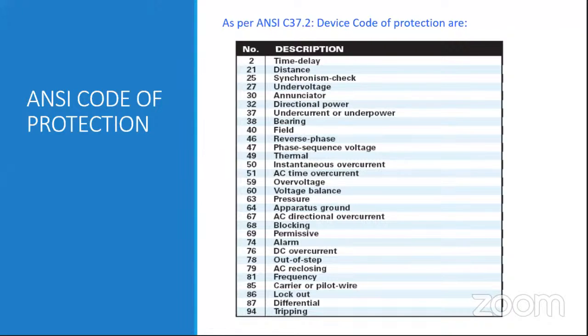Or we can say apparatus ground, in this it means the equipment ground protection. 64 means earth fault protection. REF protection is generally used for these transformers or motors. So 64 protection will take care of ground fault protection, and REF protection for transformers, generators or motors.